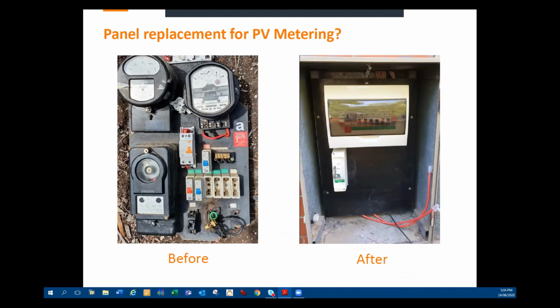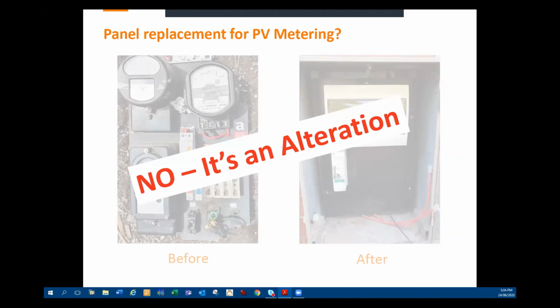So this is an example of what happened at one of the sites. The meter panel with the switchboard was just pulled off, and they've just put a new panel and screwed it to the original frame in that switchboard. So that's not really the intent of getting the site upgraded, as well as just replacing an asbestos meter panel, so it becomes a full upgrade in that sort of case. So no, it is an alteration. Something like this would have to be submitted as an alteration, and then everything can get rectified and the appropriate metering gets installed at time of the alteration.